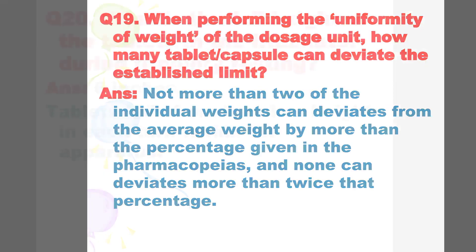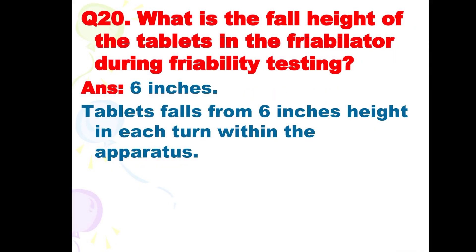And the last question is: what is the fall height of the tablets during friability testing? The answer is: 6 inches. Tablets fall from a height of 6 inches in each turn within the apparatus. Thank you.